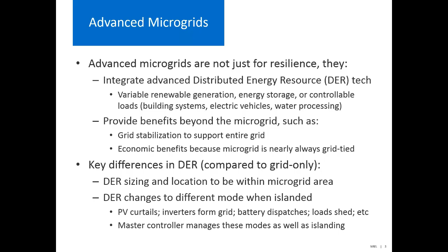Often the PV is too large for a small diesel generator to handle the ramp rates and changes, so it gets curtailed. Inverters that were grid-following become grid-forming when we go into islanded mode. And if a battery is trying to generate revenue through arbitrage or markets, once the utility goes away, there's no market anymore, so it completely changes its mode and starts managing power stability for the island itself. We might also shed some load, and the master microgrid controller manages all these changes.